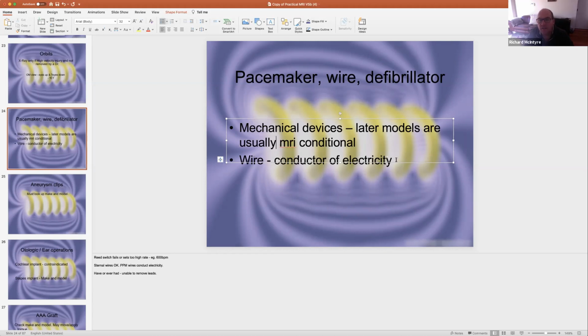They also have wires. So we mentioned that when we start the MRI machine and we put in that radio frequency, that radio frequency collects in the wire and that wire can heat up, okay? So it's very important that we check the wire to make sure that it is MRI conditional, so it's not going to heat up and it's not going to burn the patient, okay? So MRI pacemakers: the later models are generally MRI conditional. So they can be scanned, but there's a lot of work involved to get them scanned, and we have to check and make sure everything inside that patient, the pacemaker, the defibrillator, and the wires, are all MRI conditional.